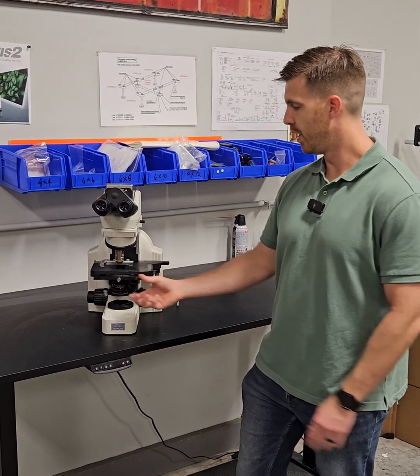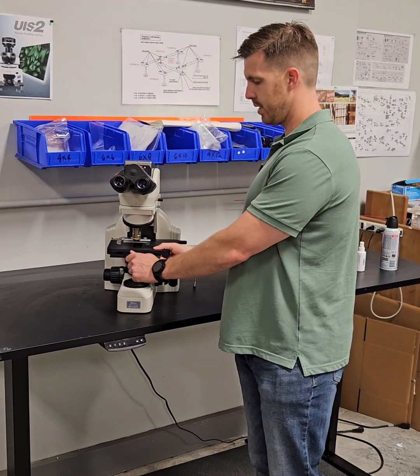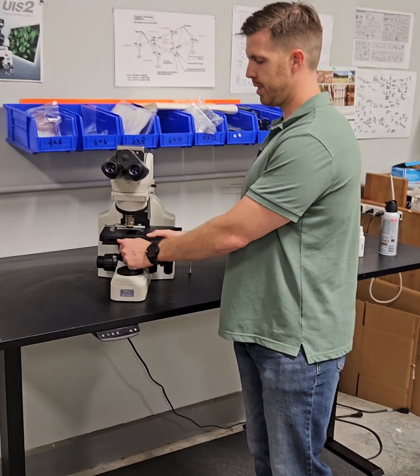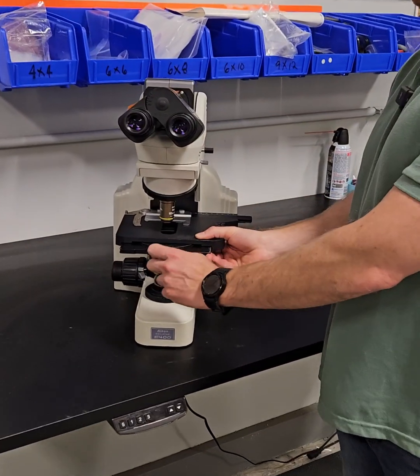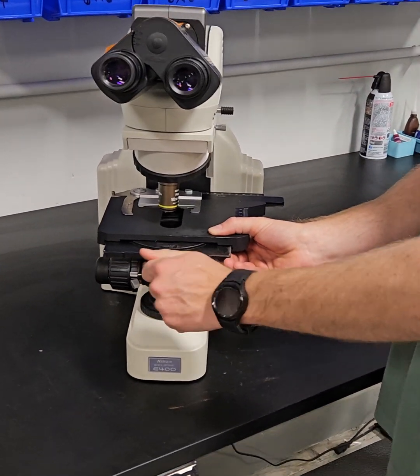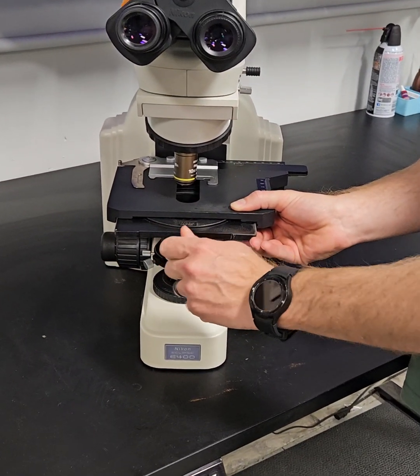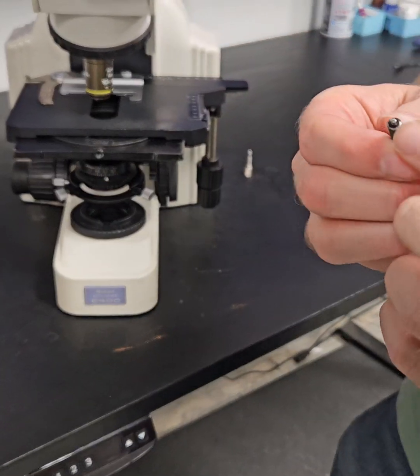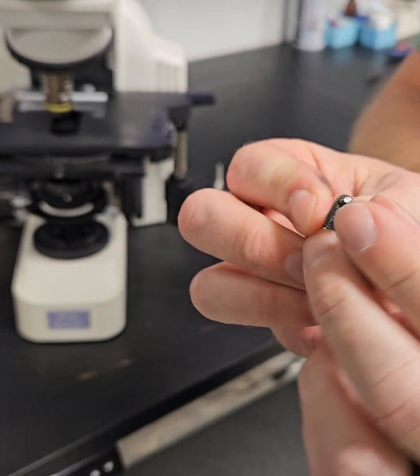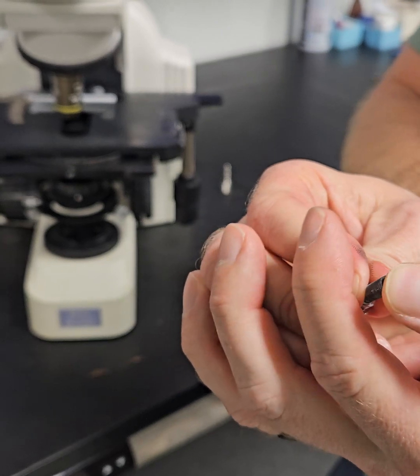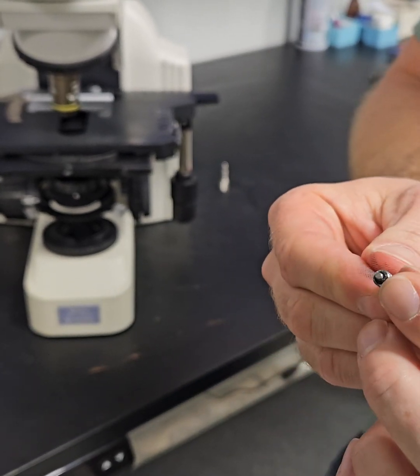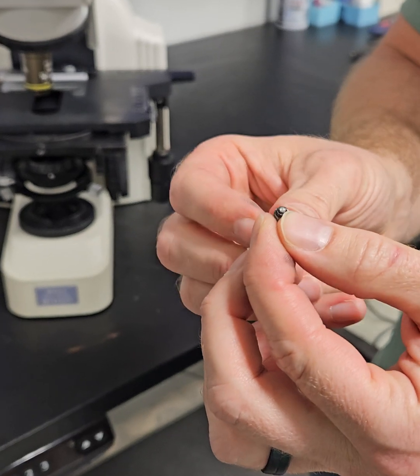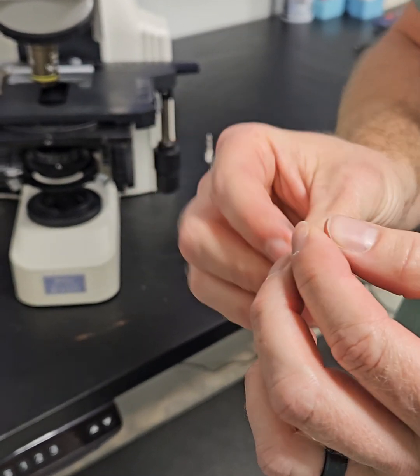This screw right here has a plastic tip and it's spring loaded. I'm going to back the screw out and show you. It had a plastic tip. See how this pin is showing? It is broken off. This plastic piece right here is very common and it breaks.